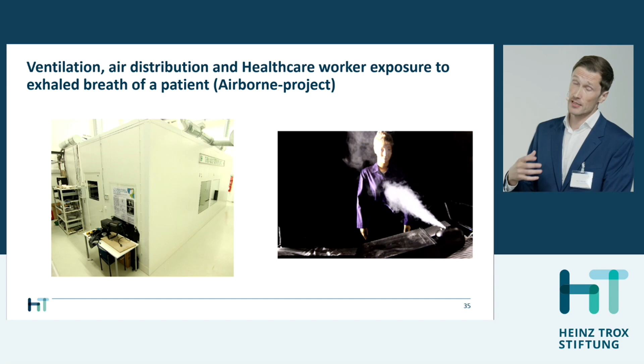So in this study, we studied this typical overhead mixing ventilation, as can be seen on the left side, as a baseline case, which is basically what is suggested in the guidelines. And then we thought, how could we improve the situation? We thought that we should include a component with improved local mixing. So we took part of the airflow in the overhead mixing ventilation case and supplied it directly downwards, not along the ceiling as in typical cases, but directly downwards to the patient bed area. We were hoping that this would give us more local mixing in the area and hence reduce the exposure of the healthcare worker to the exhaled air of the patient.